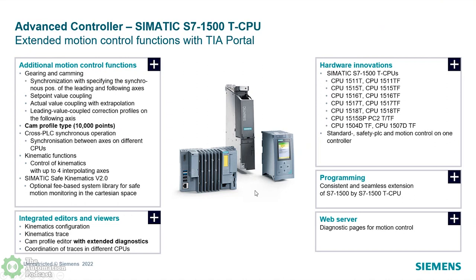While all the S7-1200 can do some simple stuff and the S7-1500 can do a little bit more advanced stuff, you really need the S7-1500T or technology CPUs to do these advanced things. Everything in that box of additional motion control functions — gearing and camming, cam profile, cross-PLC synchronization, kinematics, and safe kinematics — are all T, technology CPU features. Those are the features you get when you upgrade from the standard S7-1500 to the T or technology CPU, which is a CPU designed for high-end motion applications.